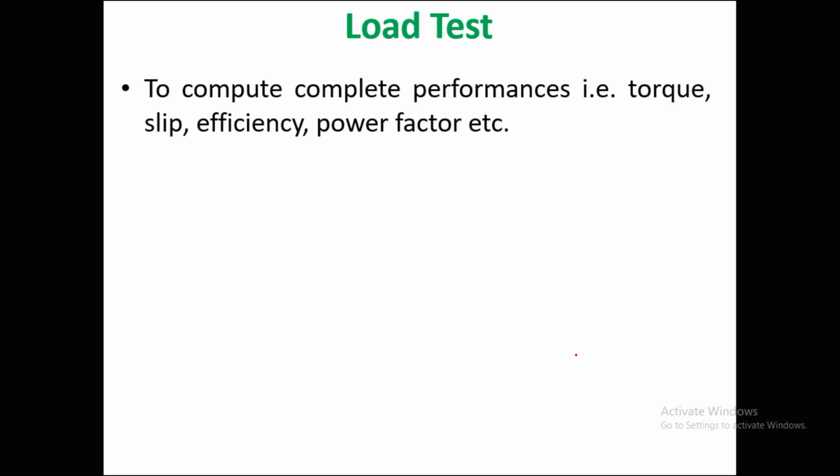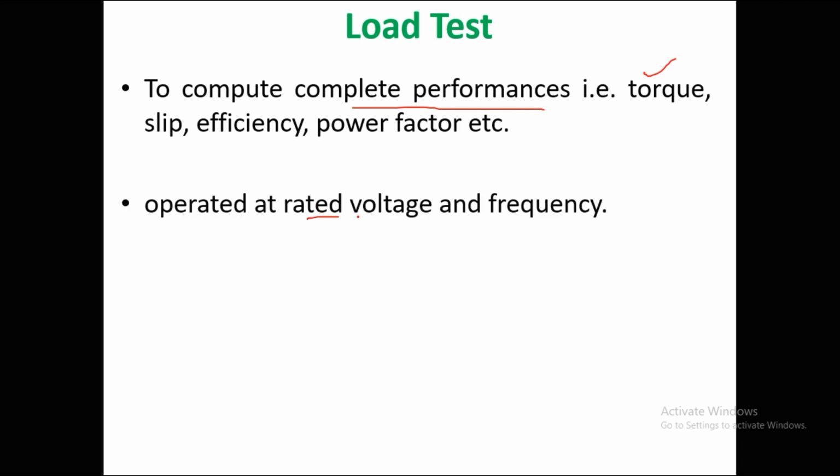The purpose is to compute the complete performance of an induction motor. We are going with the load test. Starting from the torque developed and the mechanical power developed on the rotor, the value of the slip, efficiency of the motor, rotor efficiency and input power factor, everything related to the operation of an induction motor we can obtain by conducting the load test. And while doing such a load test on an induction motor, we have to operate the motor only at rated voltage and frequency. Remember, we have to operate only at rated voltage and frequency.